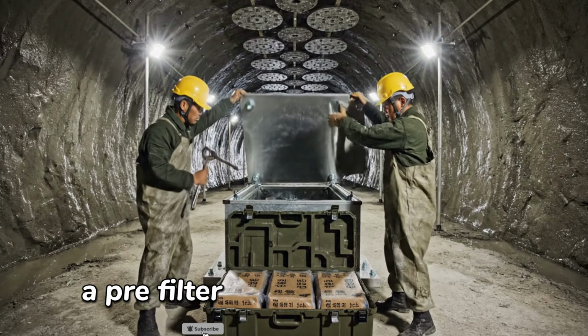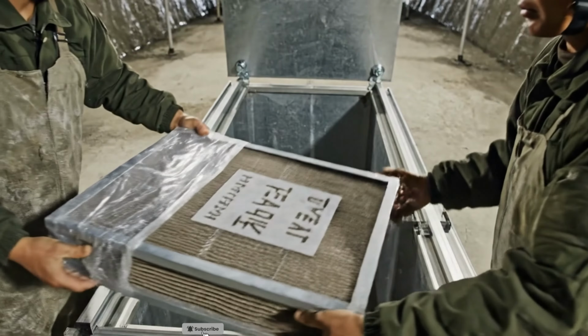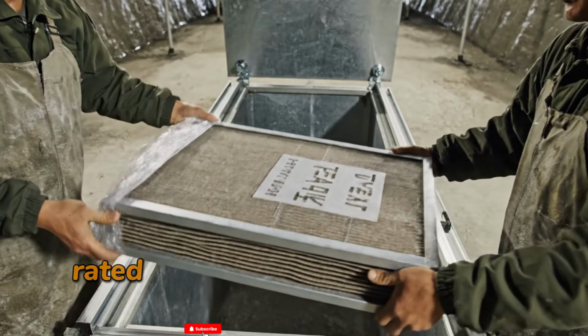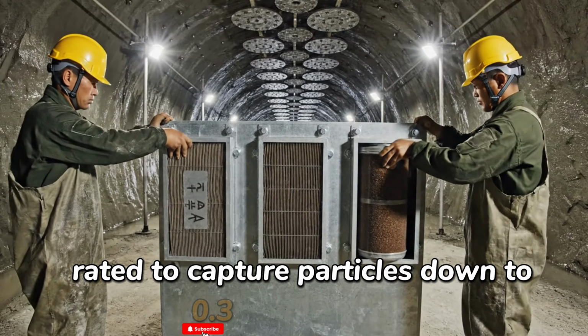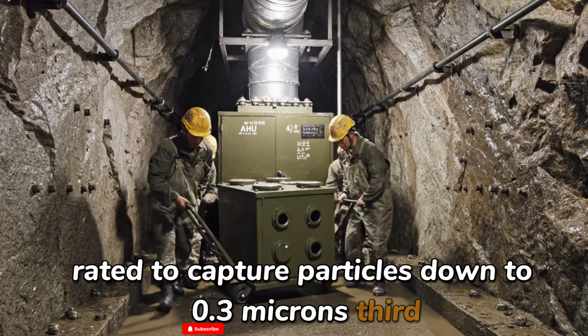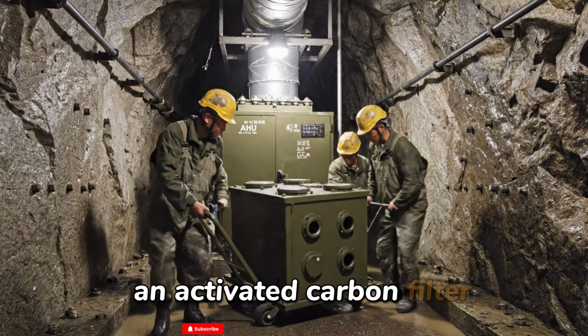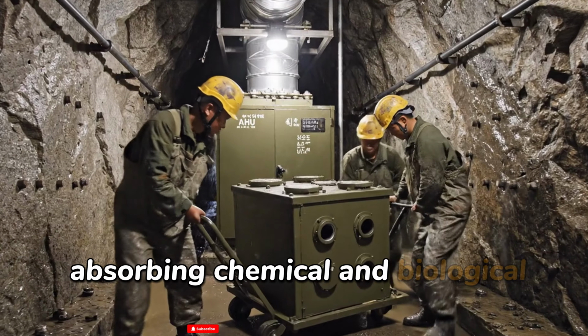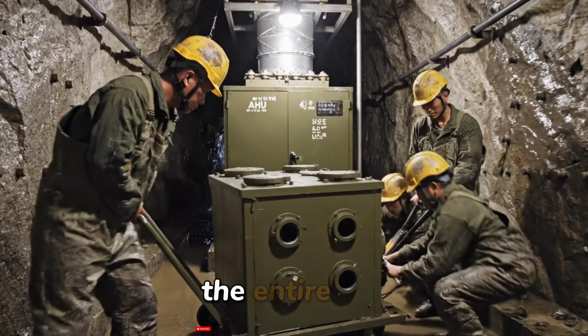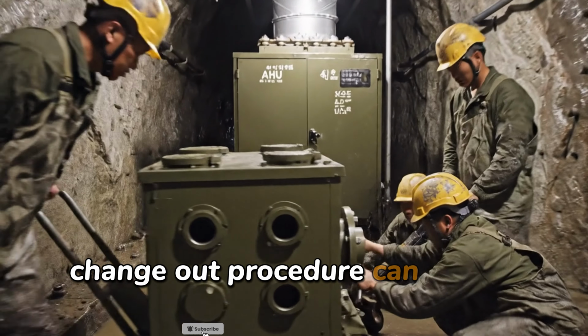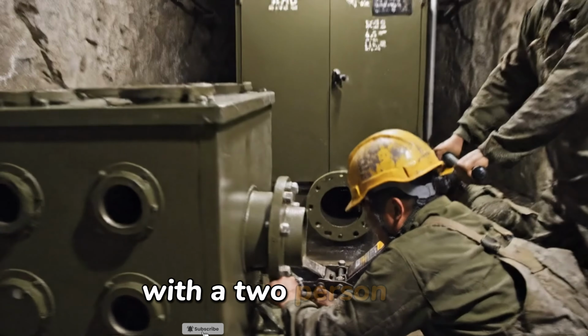First, a pre-filter removing particulates. Second, a HEPA filter, rated to capture particles down to 0.3 microns. Third, an activated carbon filter, absorbing chemical and biological agents. The entire filter change-out procedure can be done in 12 minutes with a 2-person team.